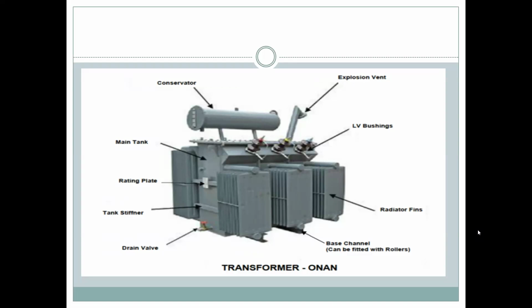Then this is the tank. This is the rating plate, with the details of the transformer. Then these are the lifting lugs, then the transformer radiator fins are there. These are very, very thin so that the cooling can be done. It radiates heat to the outside ambient and cools the oil, and it goes back. Natural convection takes place and cools down the transformer winding.